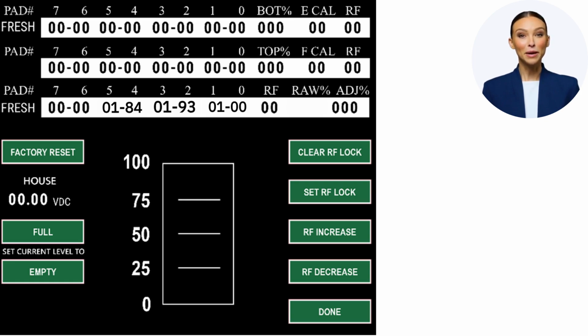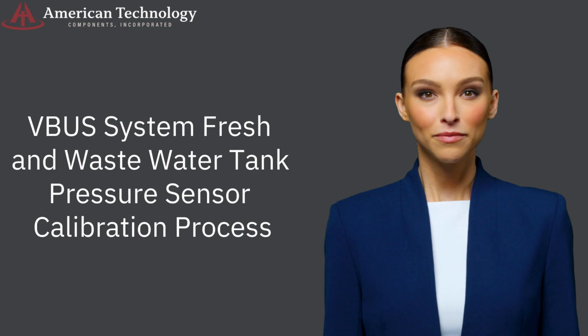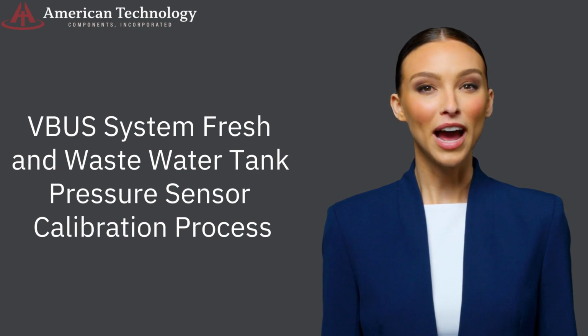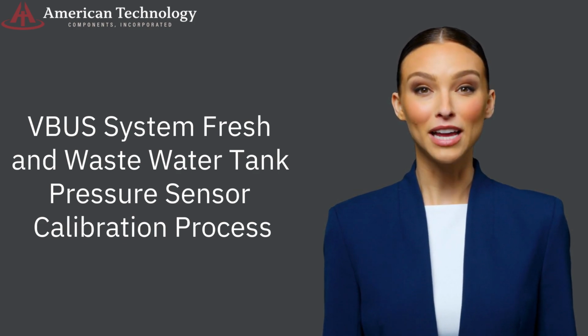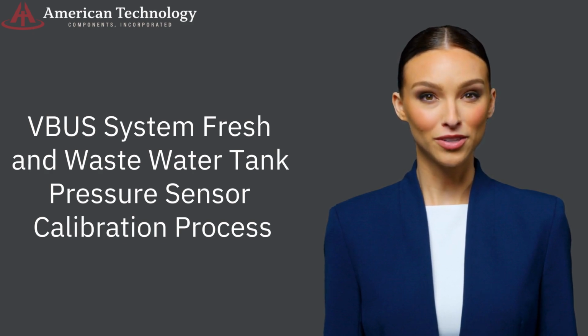It is strongly recommended to use a flow meter to gauge the amount of water being added for accuracy when setting full. Once you have filled the tank to 95% of capacity, you will see a different number under the 3 and 2. By selecting the Full button, the numbers beneath the 5 and 4 will change to mirror the numbers in the 3 and 2. This will indicate a successful calibration. This concludes our instructions for calibrating your ATC VBUS tank monitoring systems with pressure sensors. Thank you.